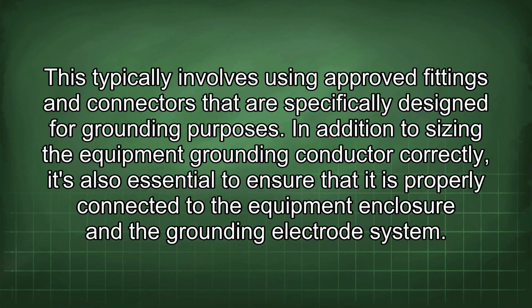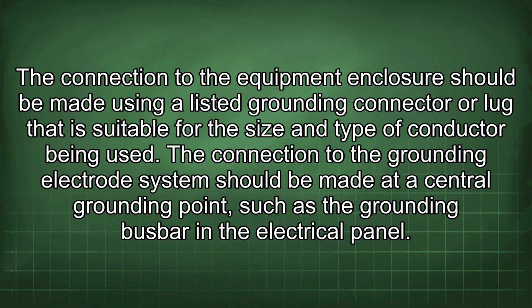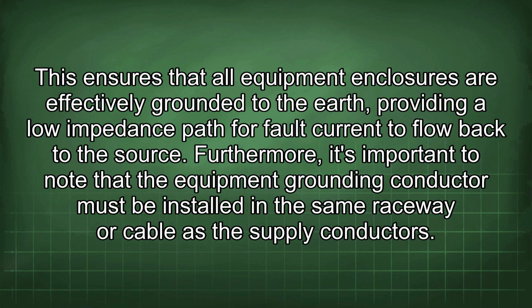In addition to sizing the equipment grounding conductor correctly, it's also essential to ensure that it is properly connected to the equipment enclosure and the grounding electrode system. The connection to the equipment enclosure should be made using a listed grounding connector or lug that is suitable for the size and type of conductor being used. The connection to the grounding electrode system should be made at a central grounding point, such as the grounding busbar in the electrical panel. This ensures that all equipment enclosures are effectively grounded to the earth, providing a low impedance path for fault current to flow back to the source.